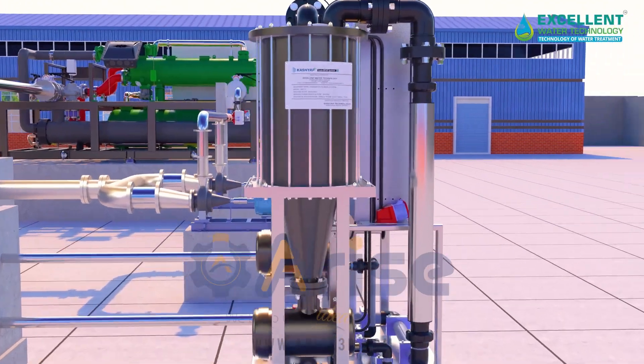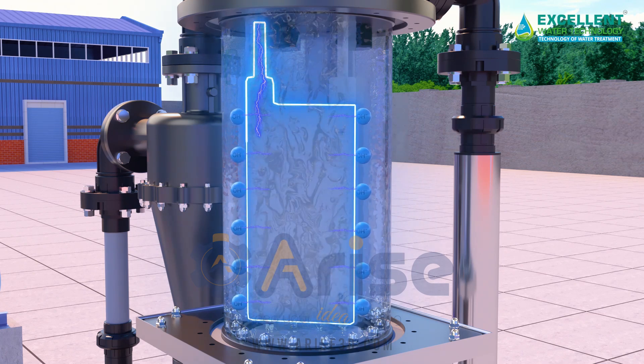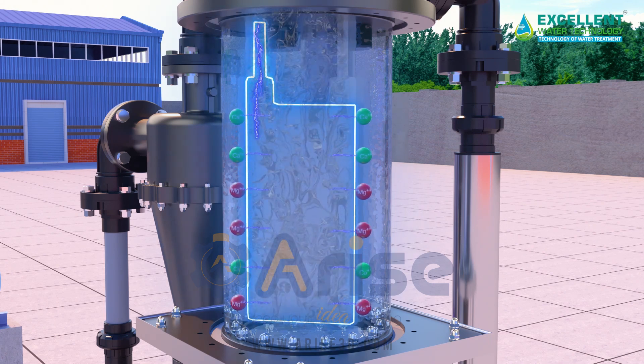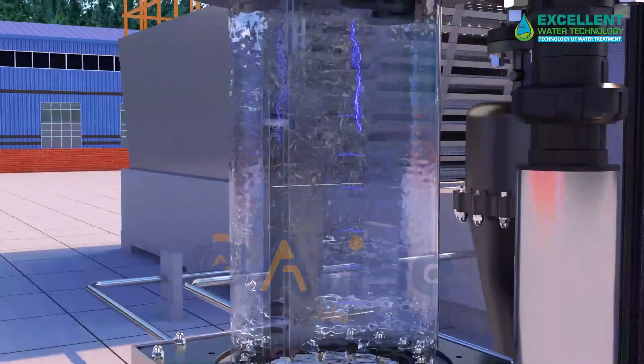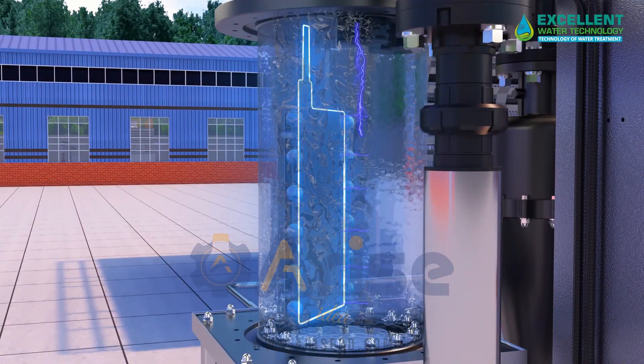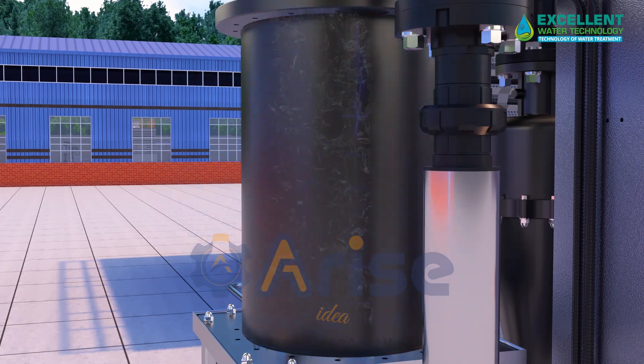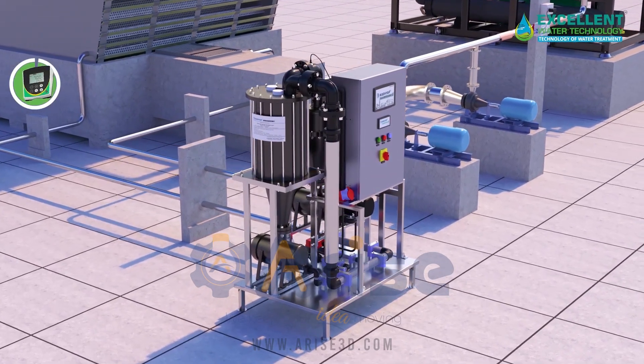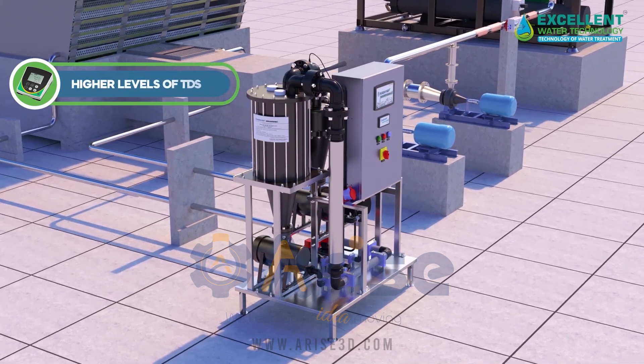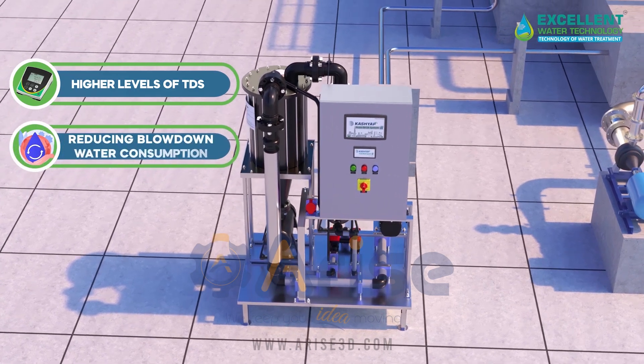The Kashup Auto BFSR system operates on the principle of water electrolysis, treating cooling tower circulation water in a specially designed electrolytic reactor. During electrolysis, DC current creates a high-pH environment at the cathode, which precipitates scale-forming calcium and magnesium salts. These deposited salts are automatically removed from the reactor at regular intervals. At the anode, chlorine and other oxidants are produced, acting as strong biocides to reduce microbial and algae growth.